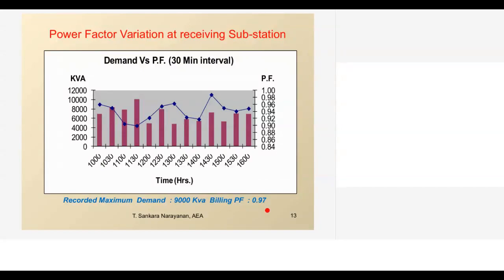Second, sometimes there is an APFC failure, because everywhere they have provided APFC and the PF is good, they thought the systems were working. So when we did the audit, we could find that in some of the substations, certain APFC panels are not in service. They are not making any difference, because whatever set point is there, it is that capacitor bank only. There are no additional capacitors added or deleted as per the load. So we have to review this. That is why we always tell you to monitor the peak power factor and check whether the APFC is really taking care of the peak PF requirement.